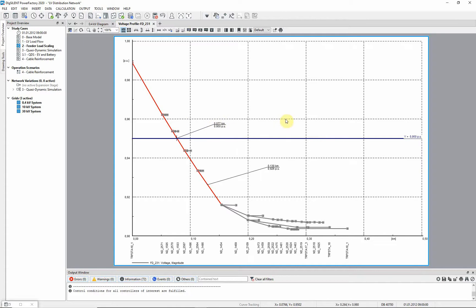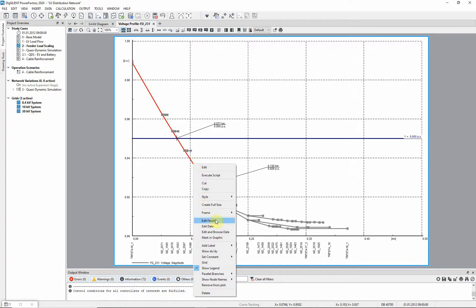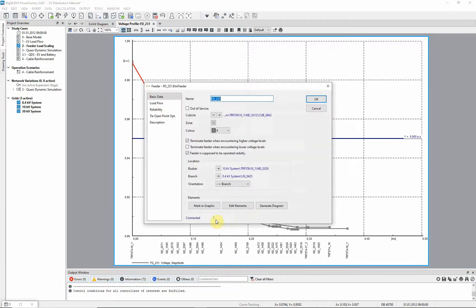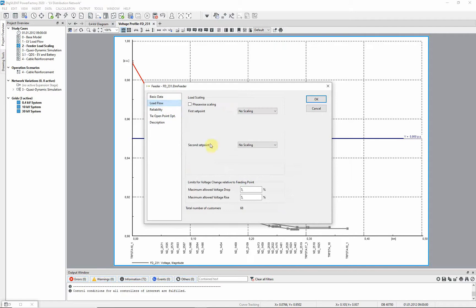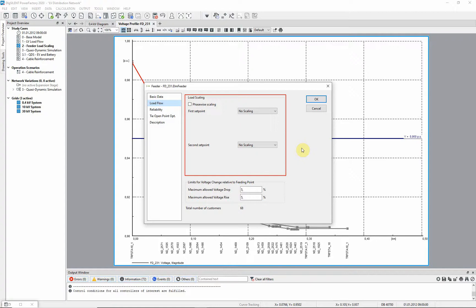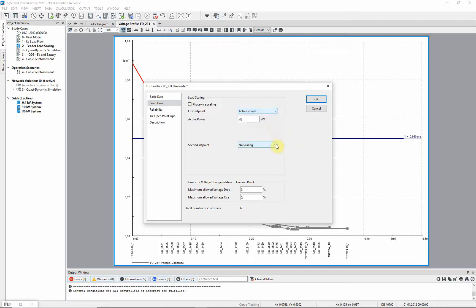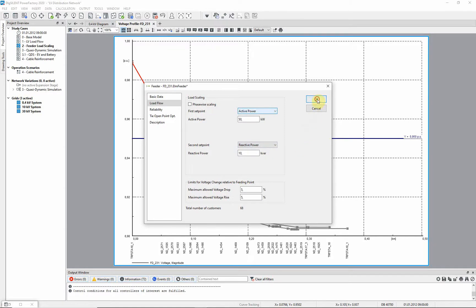You can edit the feeder directly from the diagram. Right click on the characteristic, and select Edit Feeder. On the Load Flow tab you can see that it is possible to apply load scaling to the feeder. Load scaling can be used to scale individual loads connected to a feeder so that they comply with an overall value for the feeder, which is specified in this load scaling section of the feeder object. For the first set point, select Active Power. And for the second set point, select Reactive Power. Set the active power to 50 kW and the reactive power to 10 kvar. Select OK.